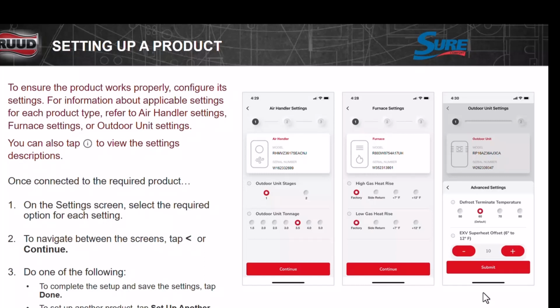Advanced settings. On a heat pump, you can go set the defrost termination temperature. It comes right here at 60. I would leave it there. For our area, we don't need anything more than that. But it is adjustable for you to do.